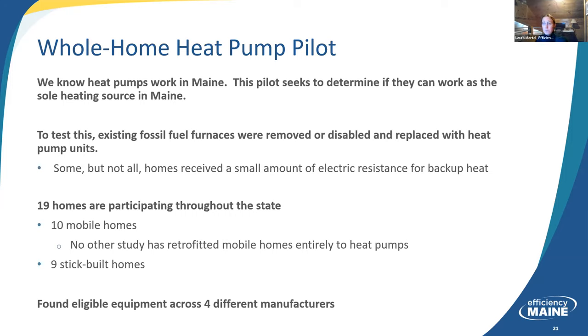So there are 19 homes participating in this throughout the state, 10 of which are manufactured homes and 9 of which are traditional stick built. And in all of these homes, we have either disabled or removed the fossil fuel system. They do not have a fossil fuel system to fall back on. Some of the homes have a heat load such that the design load of the heat pump is not exactly where we want it to be. We talked about how it's important to size the heat pump for the load of the home.